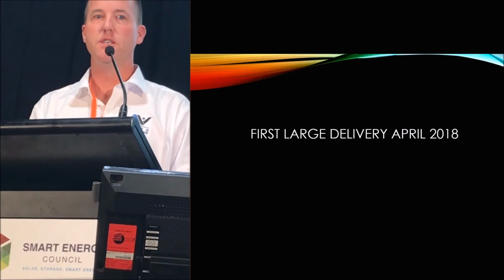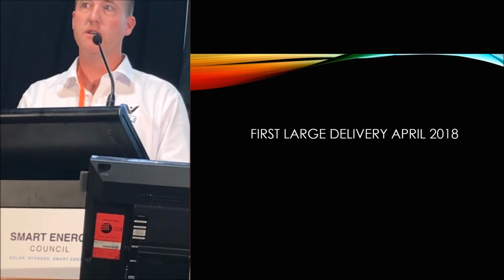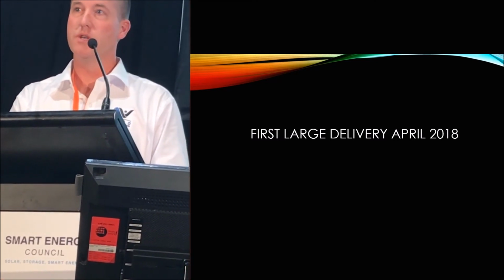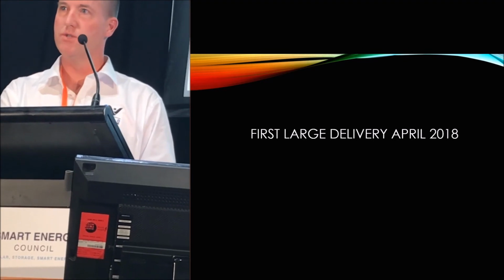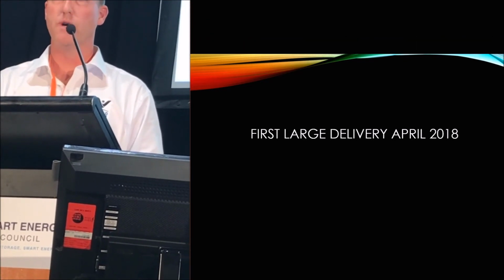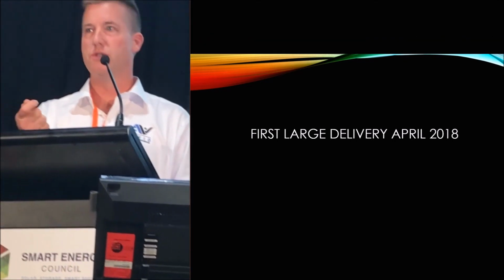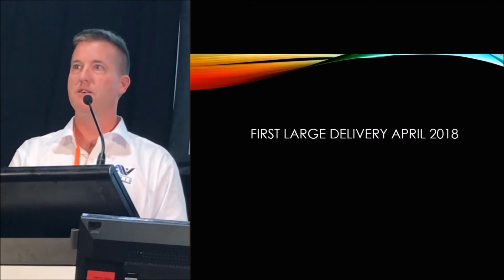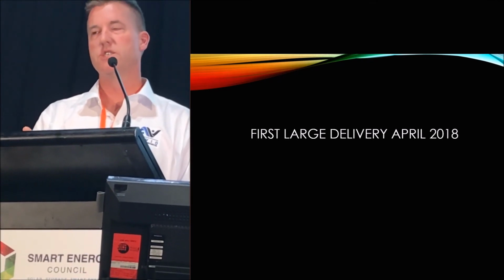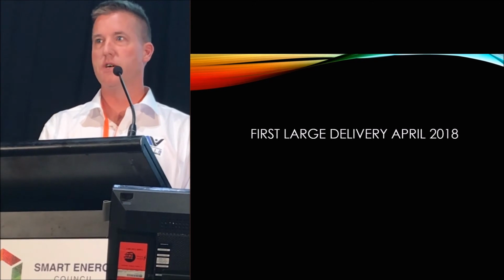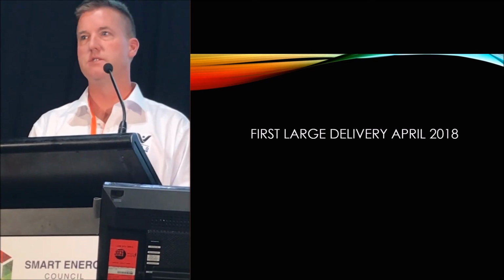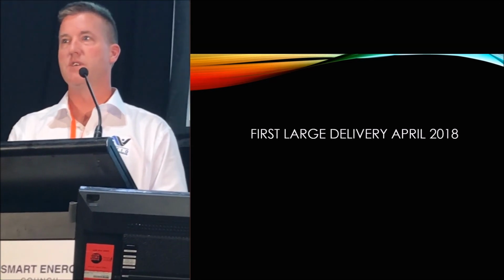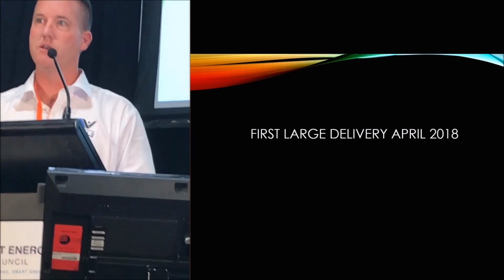But the energy, there's no thermal runaway. So if you short the cell out, it'll just waste all its energy really quickly. The short circuit, I've done a short circuit current test on the cell, which might be a good way to answer the question. We dead shorted the cell with a copper bar and just ran it to zero. It actually damaged the cell a bit because it was so fast to discharge. It discharged in about 15 seconds, but the cell emptied all its energy in one go. It got hot and then it cooled off again.